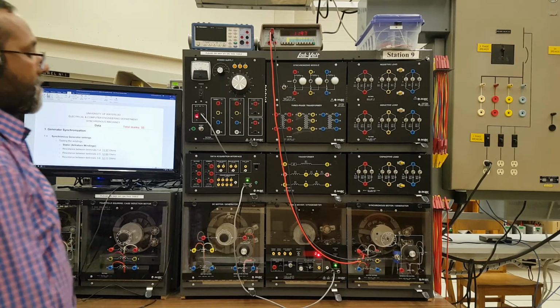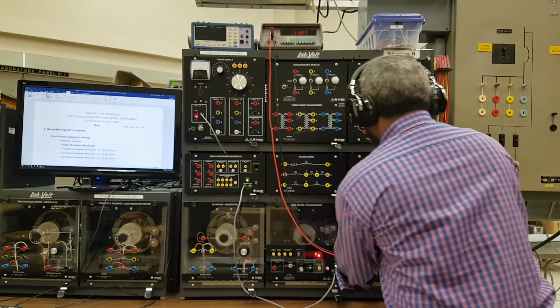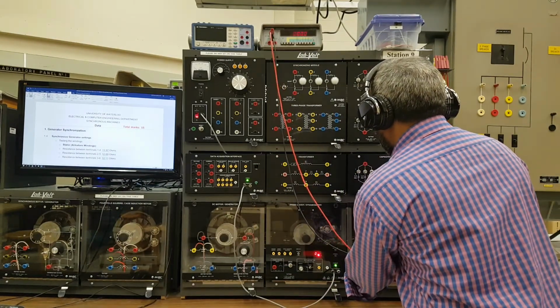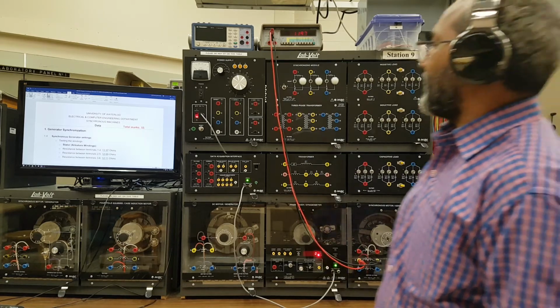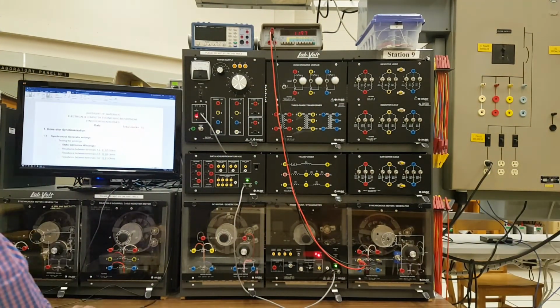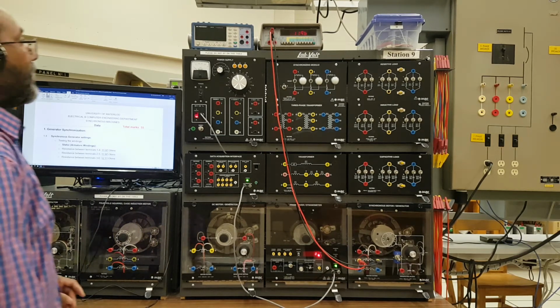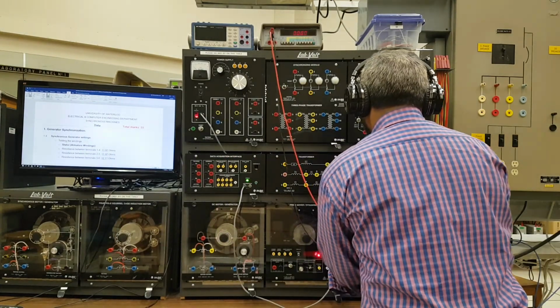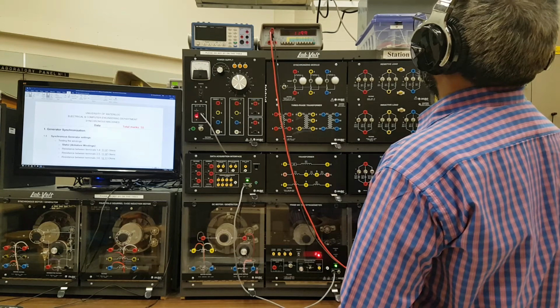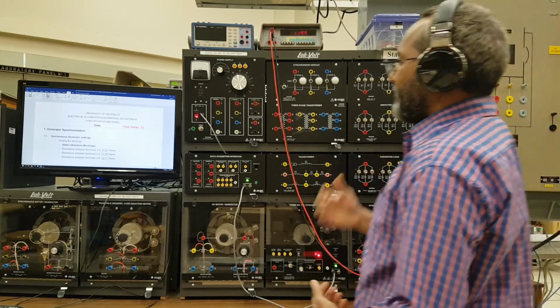Control S. And the next winding is 11.97. That's very good, that means both are equal. So 11.97 again. And then the next one is 11.99.